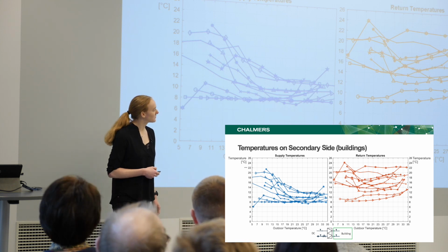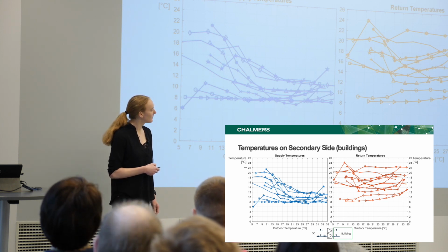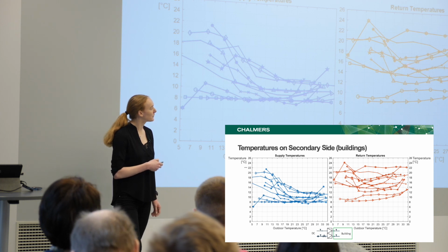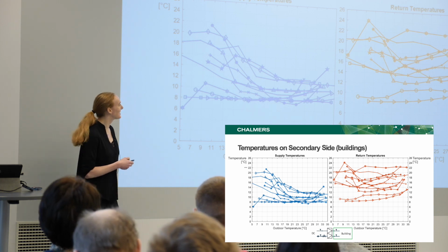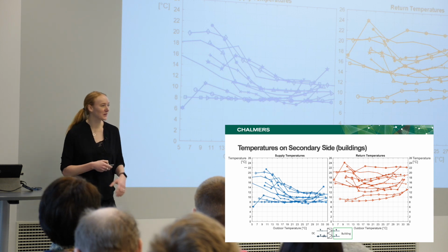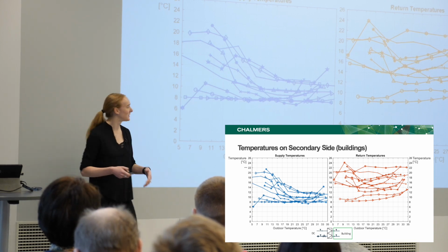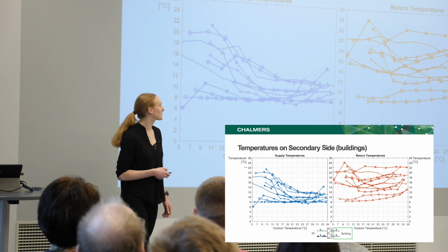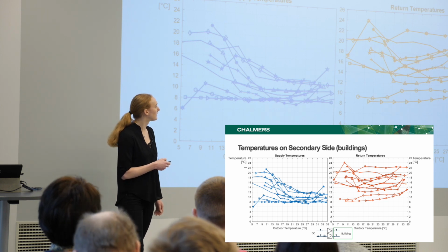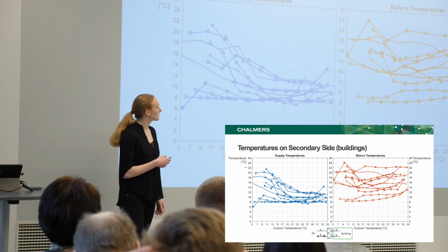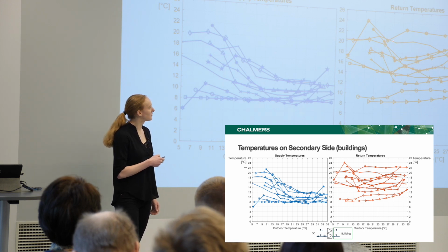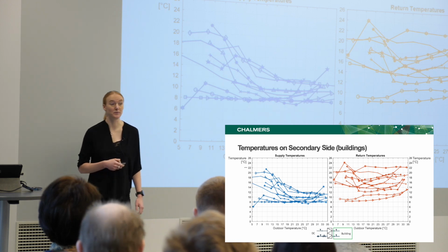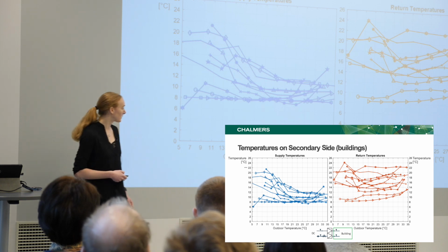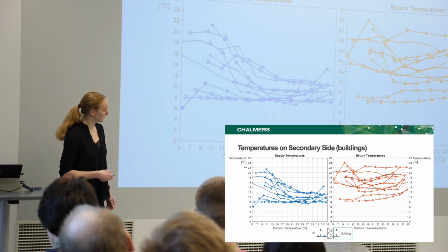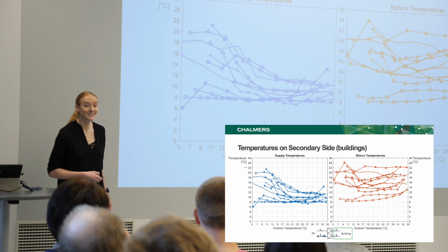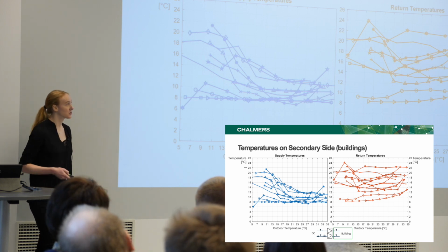But when it comes to the return temperature side, there is everything, basically. And you have 18 up here. So there are both lower temperatures and higher temperatures. And of course, this is a problem, that there's such a wide range here. And of course, it's positive for these buildings that have higher return temperatures than the requirements. So this is, I should have mentioned this before, on the building side of the heat exchanger, what you see here.